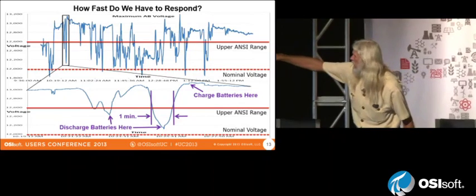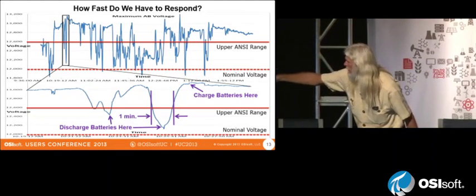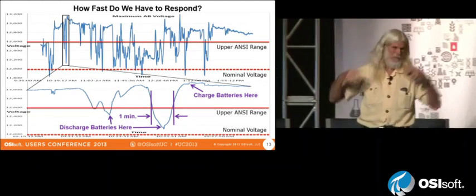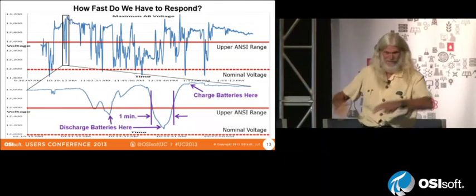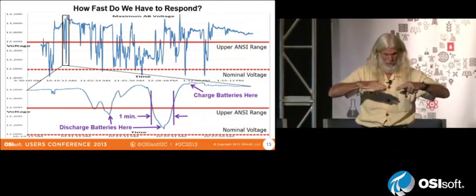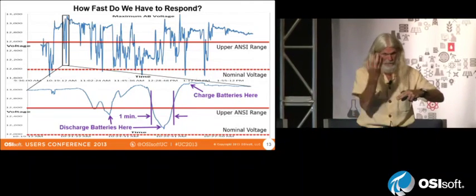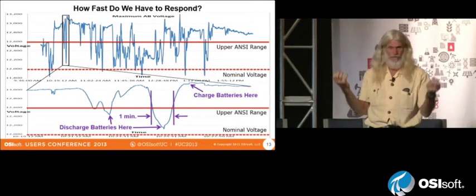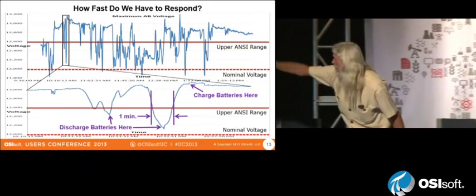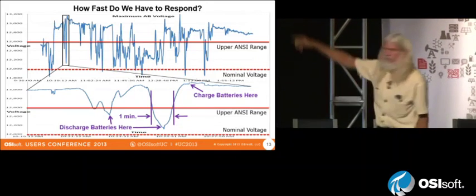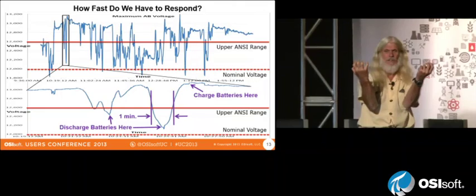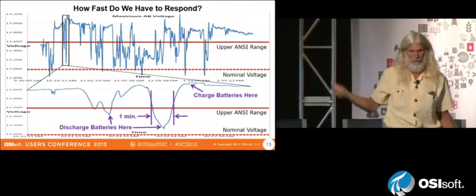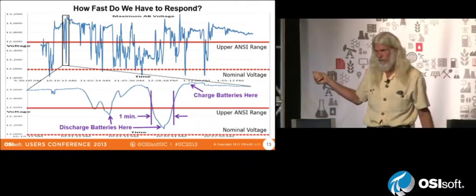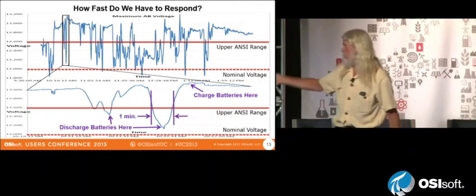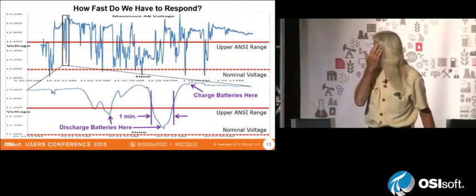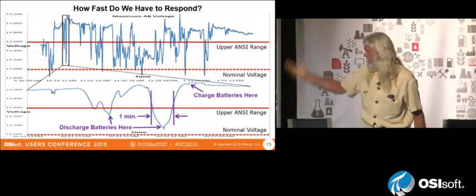Keep in mind, when that voltage is dropping rapidly, all of the grid tie inverters, which are what's causing this to begin with, see the voltage drop, which means their current goes up, which makes the voltage drop even more. The same thing happens the other direction: when they see that voltage rise real quickly, they automatically reduce their current. So in other words, they're creating more instability. And we're talking about many megawatts of solar coming out here that are basically designed to make the system unstable.